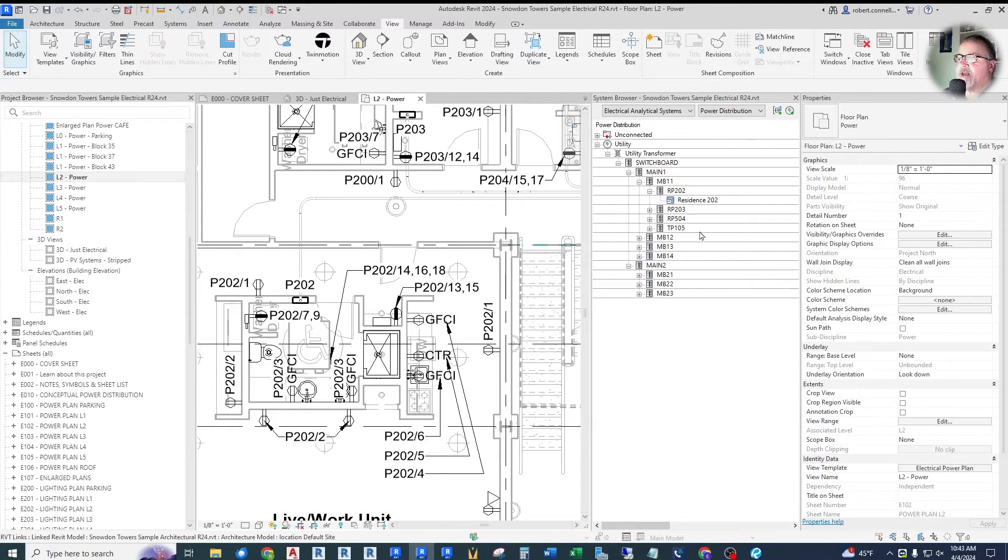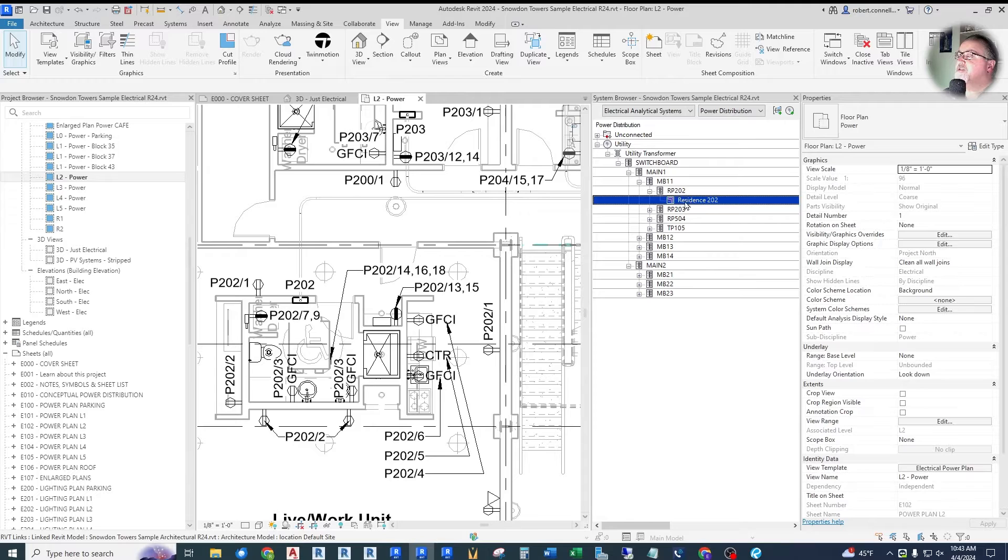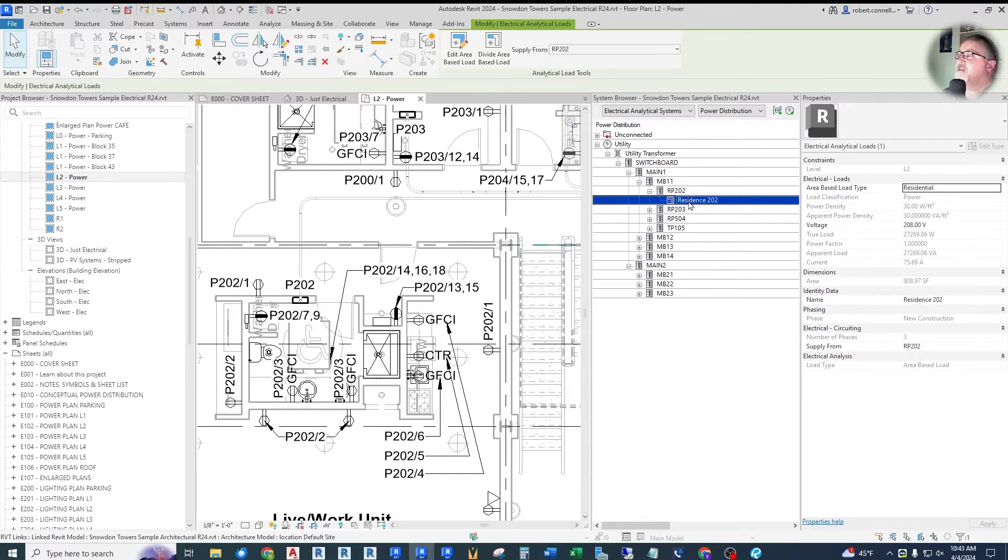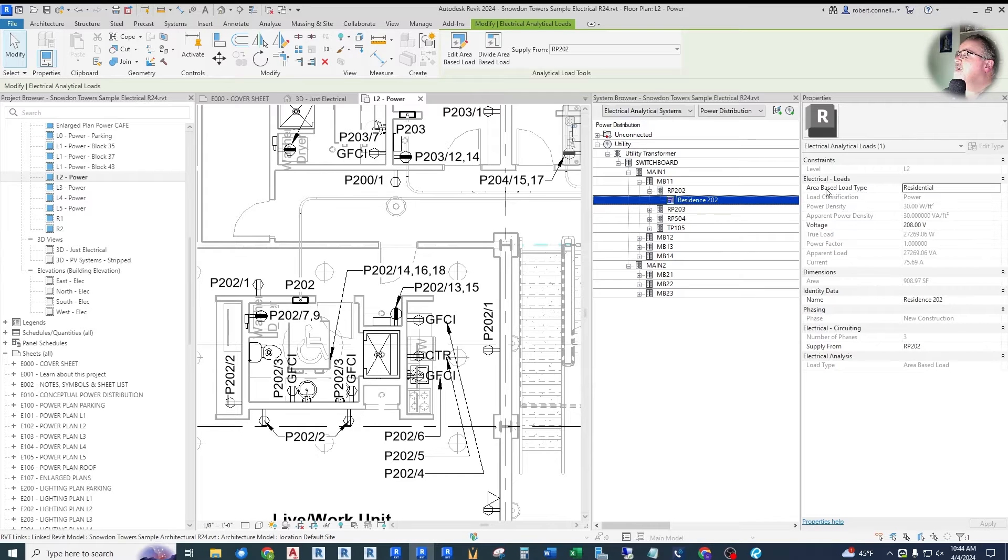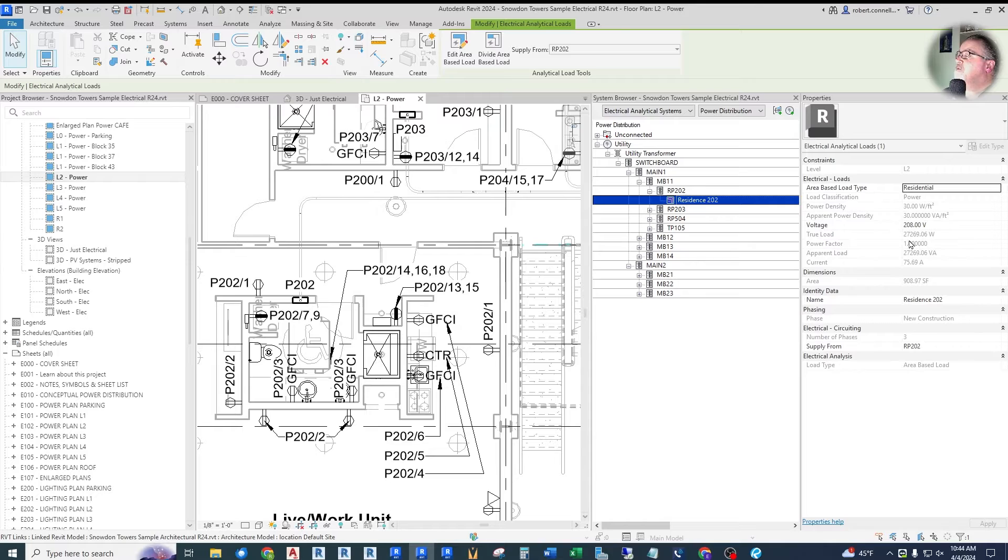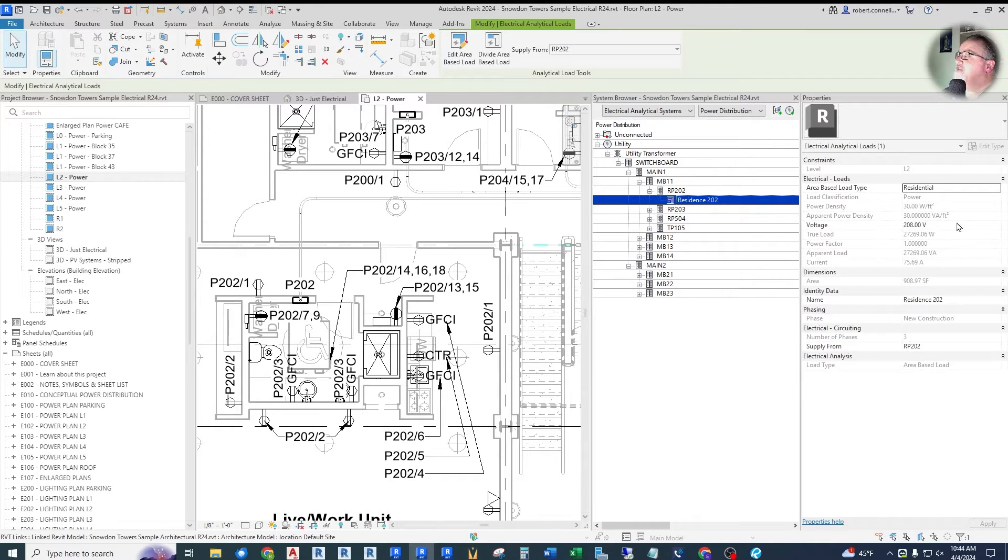So for example, this project has some single phase residences, you click here under Residence, and this is again under the analytical system, not the actual connected equipment or panels. There is this residential load, power density, 30 watts per square foot. The voltage is set at 208 and that's it. There is no single phase, three phase differentiation. It's all computed at three phase.